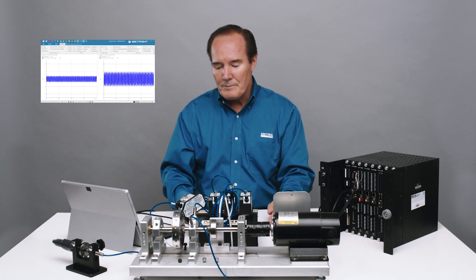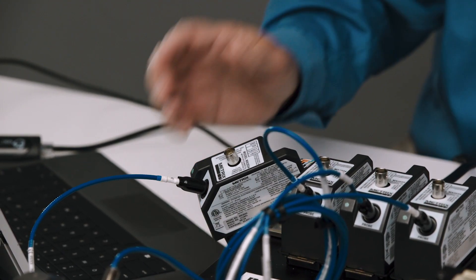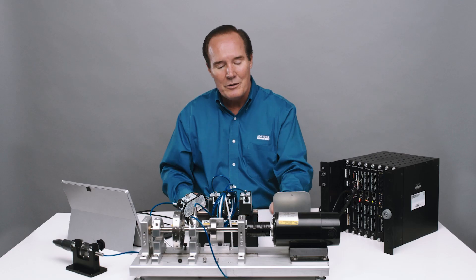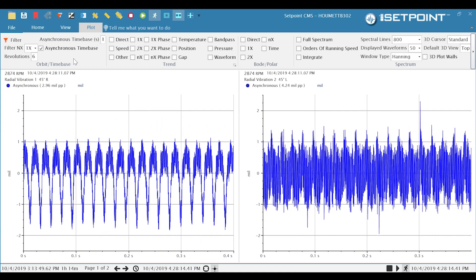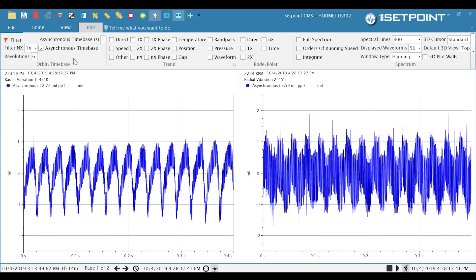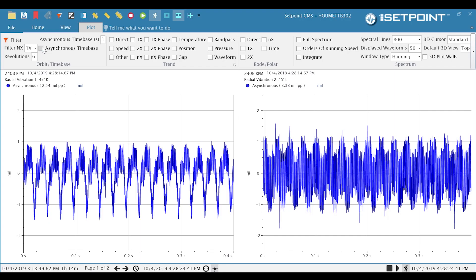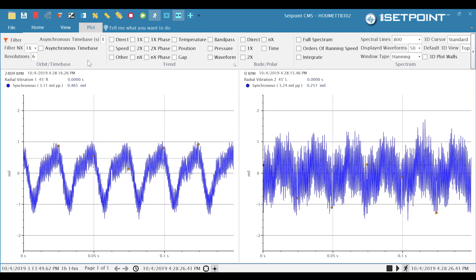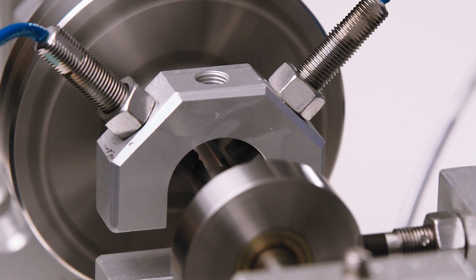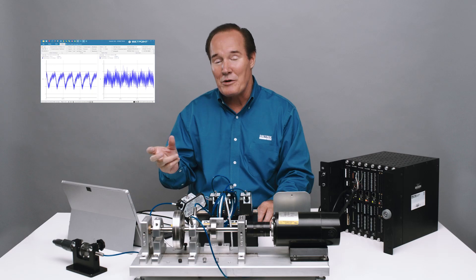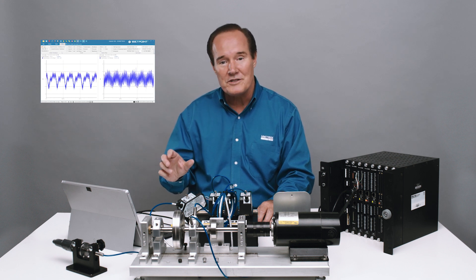So now what are we going to do about it? I'm connected to this system and I can change its frequency. But before I do, let me go ahead and start up this rotor and show you what a noisy signal looks like when it's vibrating. Now this machine — I'm asynchronously sampling. I'll put a phase trigger in there and we'll synchronously sample. When that updates, you'll see that instead of the phase trigger being stable, it will be moving. The signal itself looks very scratchy — there's a lot of noise on it, and that's all bad. We want to actually get rid of that. This is the problem that noise causes in your signal.